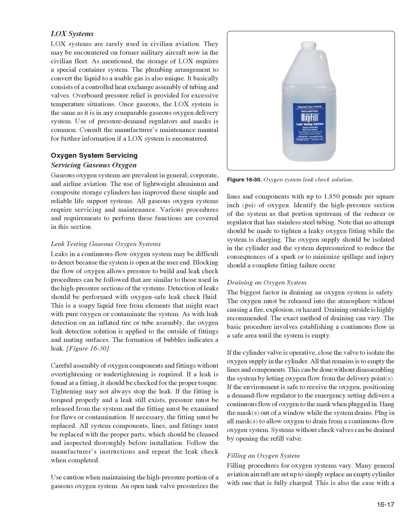Figure 16-30. Careful assembly of oxygen components and fittings, without over-tightening or under-tightening, is required. If a leak is found at a fitting, it should be checked for the proper torque. Tightening may not always stop the leak. If the fitting is torqued properly and a leak still exists, pressure must be released from the system and the fitting must be examined for flaws or contamination. If necessary, the fitting must be replaced.